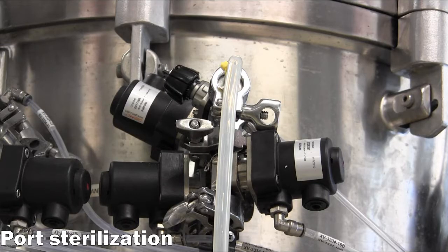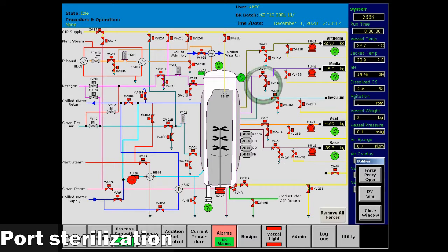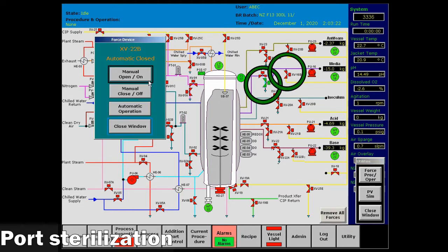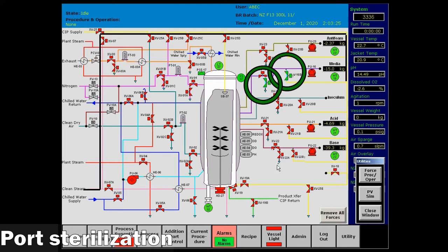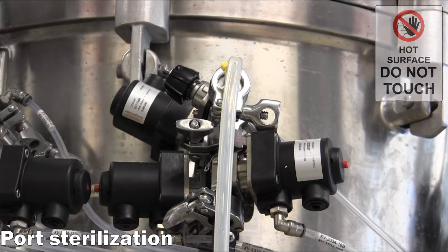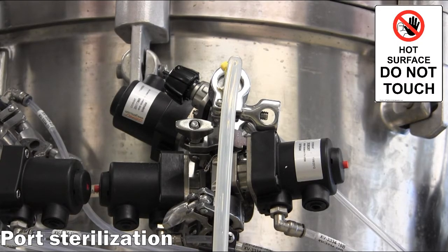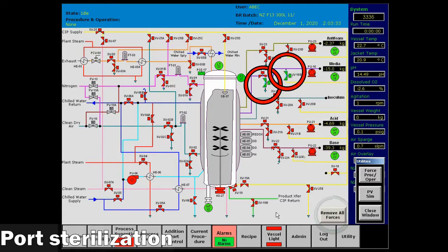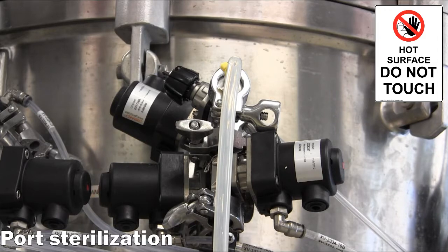To sterilize the port, go to the Addition Port Control window on the HMI. Find the port that the new assembly is on and manually open the 2 valves as shown to start the port sterilization. After 20 minutes, press the Remove Forces button to shut the valves and stop the sterilization procedure. Allow for at least 5 to 10 minutes to cool.